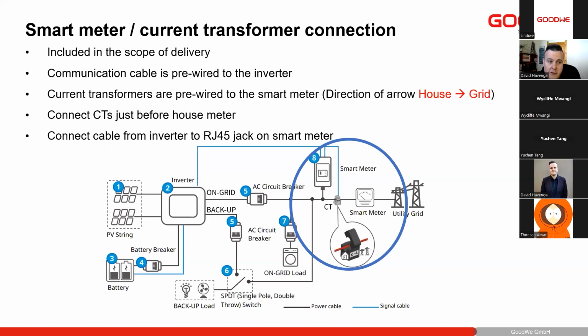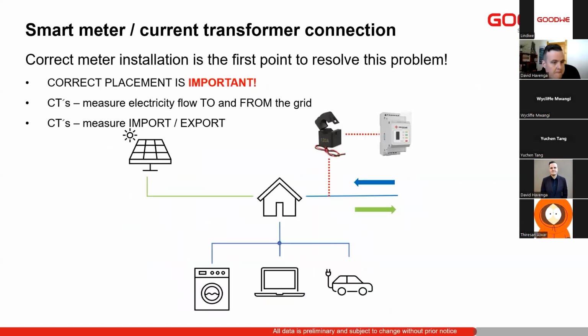So the placement is very important. Your smart meter needs to be installed and powered by the grid, so as close to the utility meter as you can. So install the meter, the meter's power supply, as close to the utility meter as you can, and then the CT in the same position as well. I'll go a bit more into depth into the smart meter, as well as show the three-phase smart meter, because that's normally where a bit of our problems come from. It's very important, the meter installation.